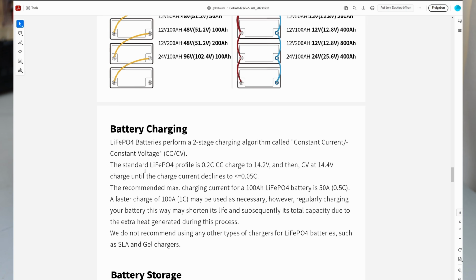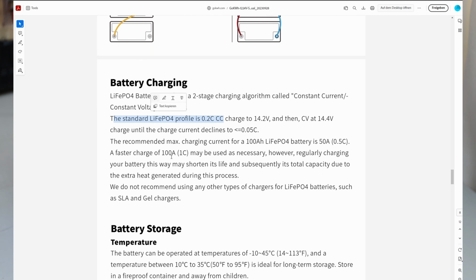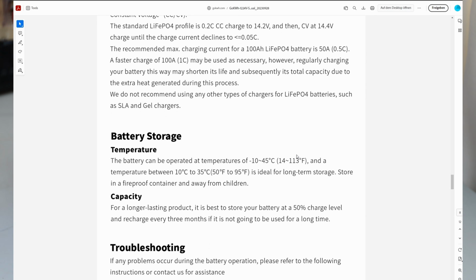Good, then we have the battery charging, and the standard lithium iron phosphate is 0.2C charge, so for 100 amp hours, 20%, 0.2C would be 20 amps. A faster charge of 100 amp, 1C, may be used as necessary. Yeah, you can do that, but it might also degrade your battery over time. Keep that in mind. The battery can be operated at temperature, that's good, so they tell you.